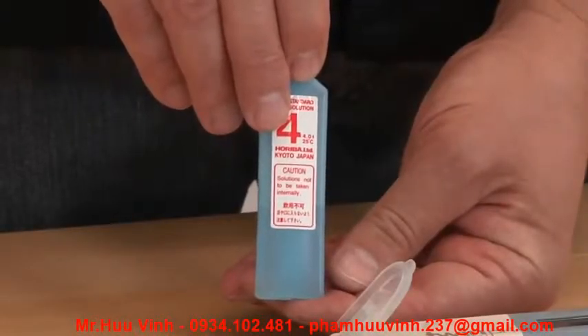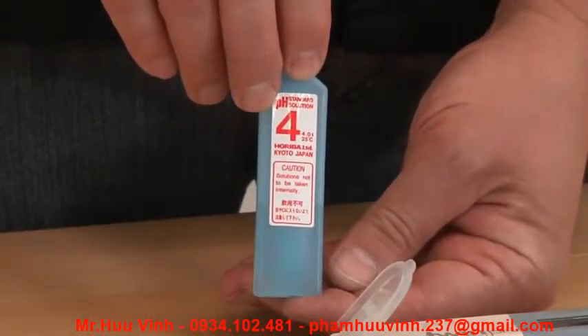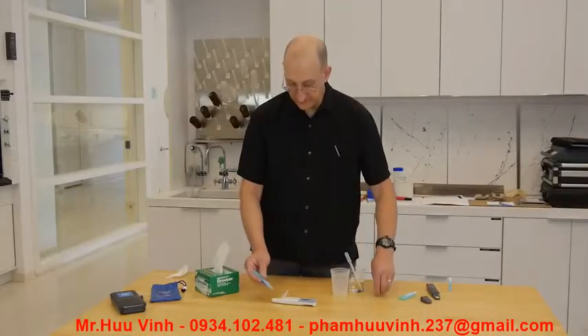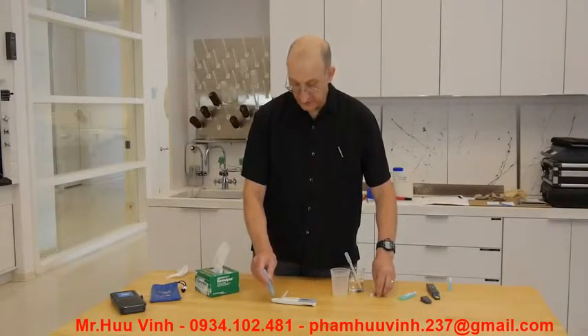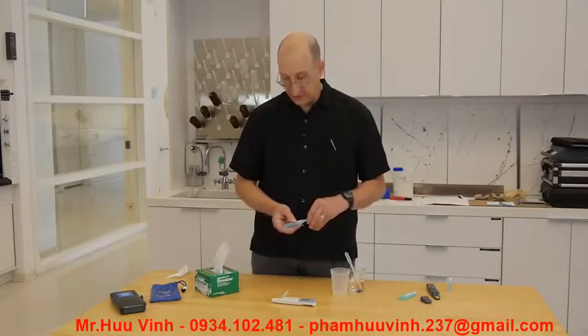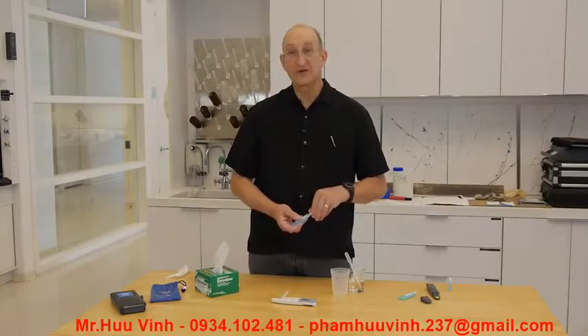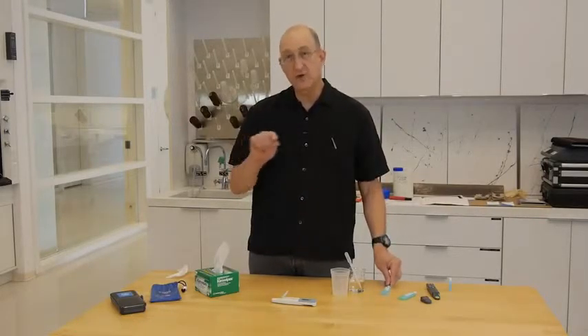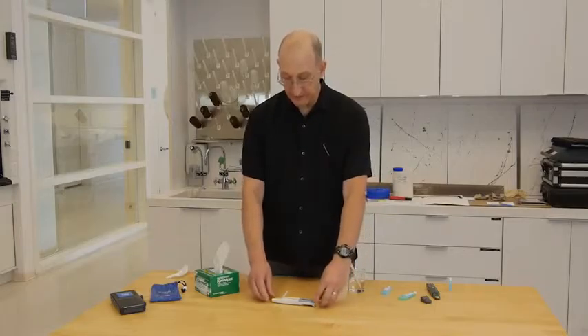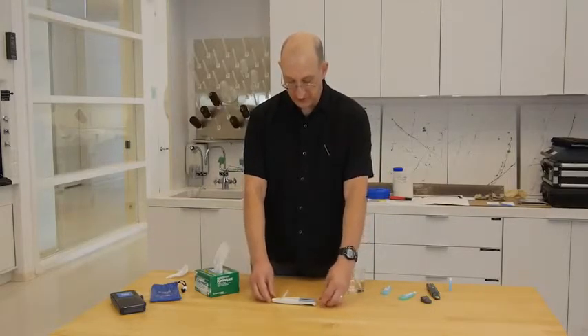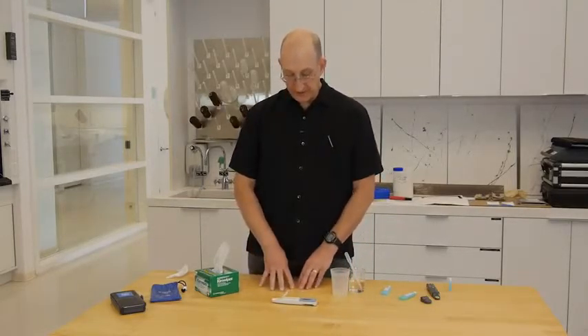Now we want to calibrate at pH 4, use the pH 4 buffer solution. Again, fill the sample well. Make sure we have both the measuring and reference electrode dampened, and we have both in contact with liquid. The liquid is consistently across. Again, we wait for the happy face.